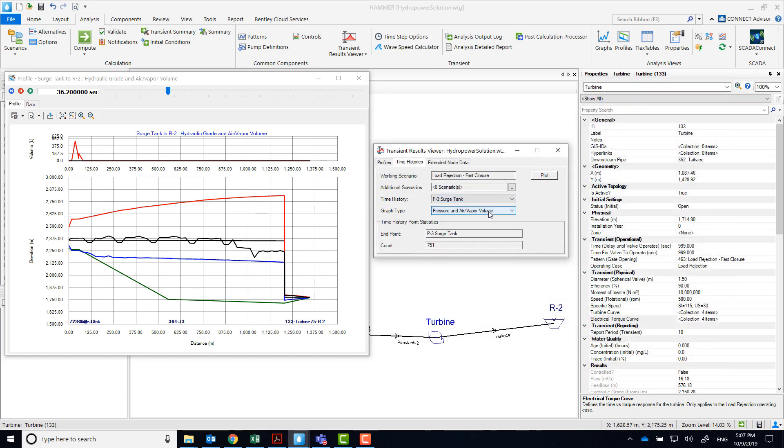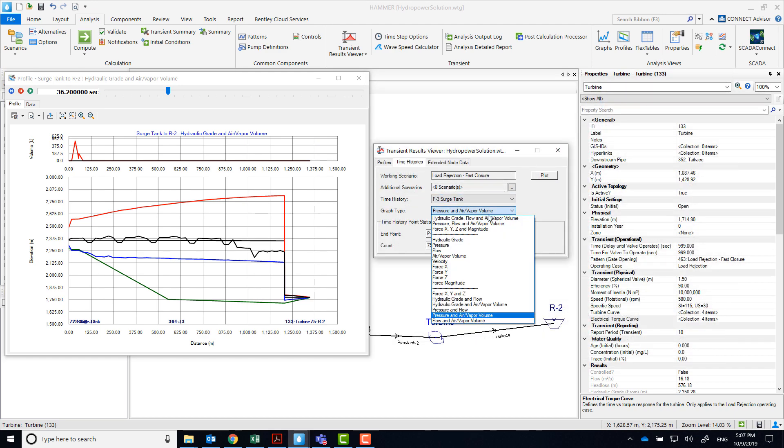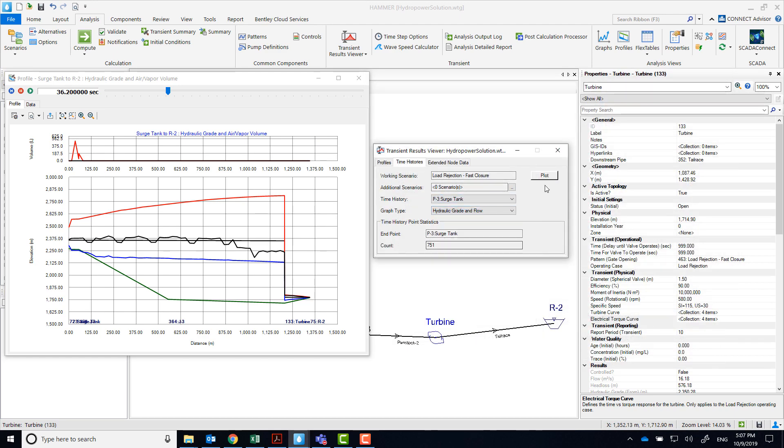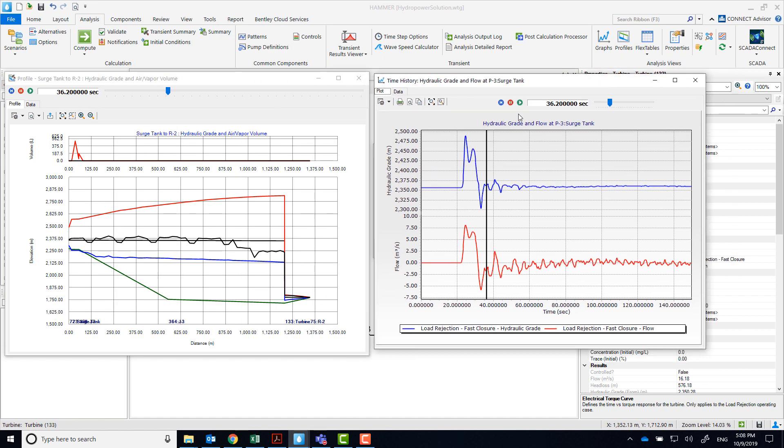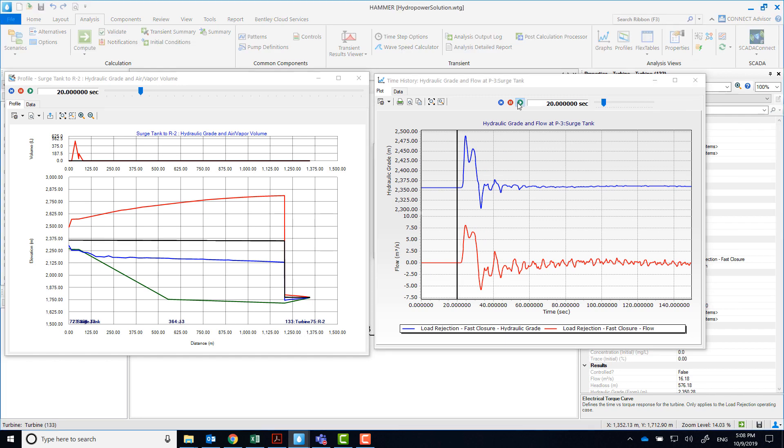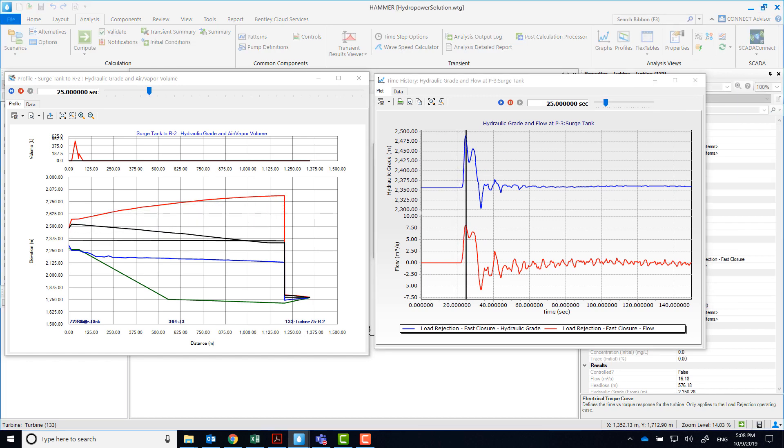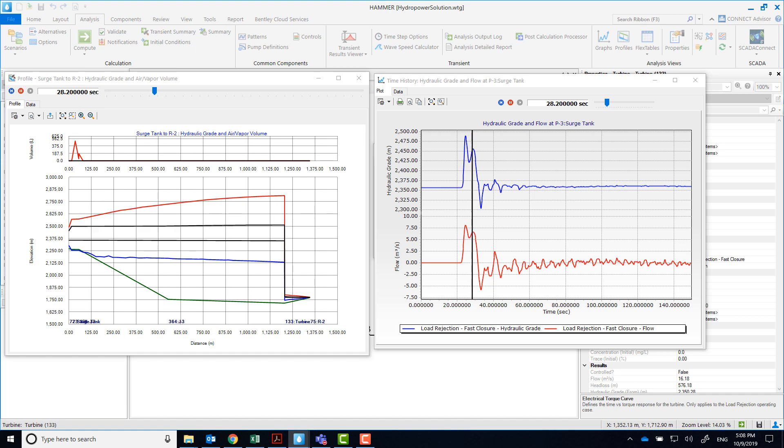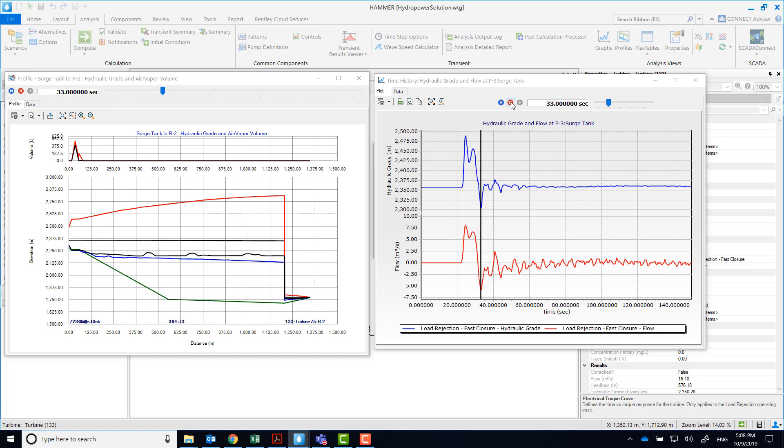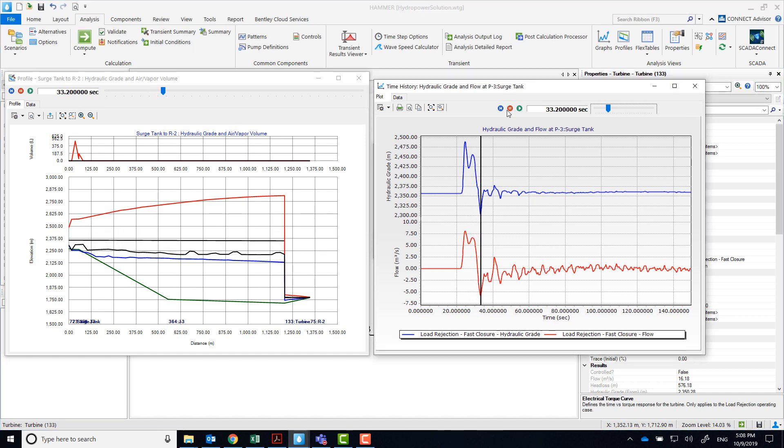Let's observe what happens near the surge tank. Take a look at the head and flow. Notice that following the closure of the wicket gates, the pressure spikes and the flow goes towards the surge tank. And then at about 29 seconds, it starts to drain.